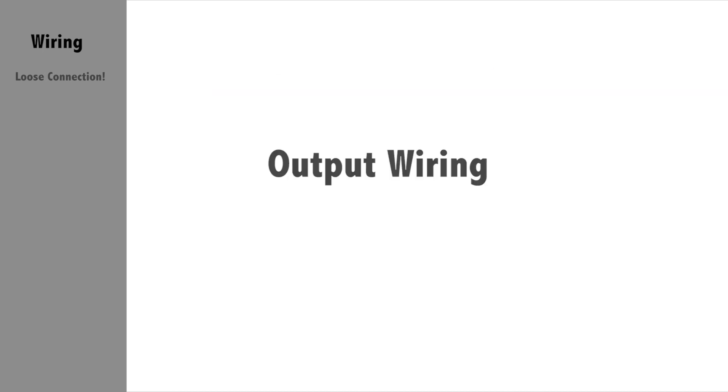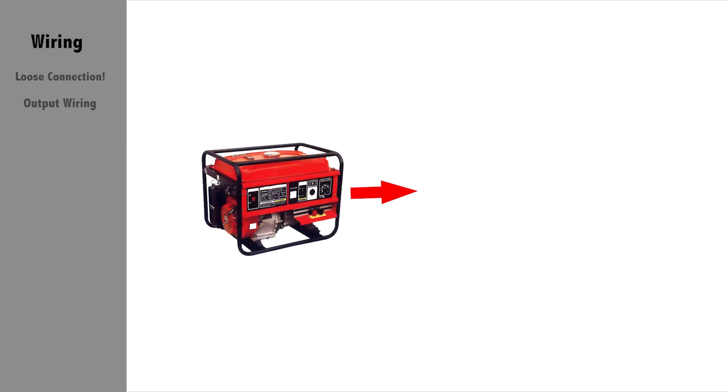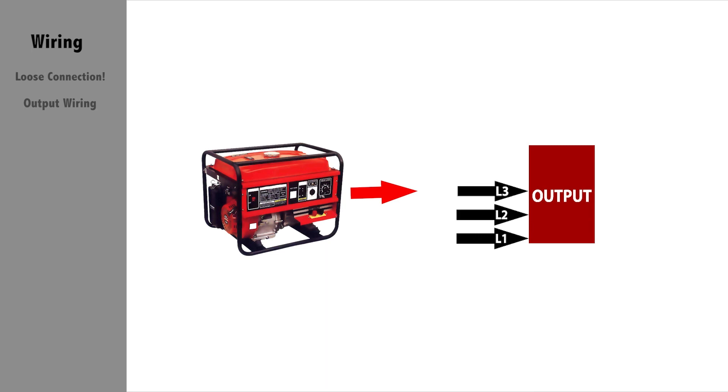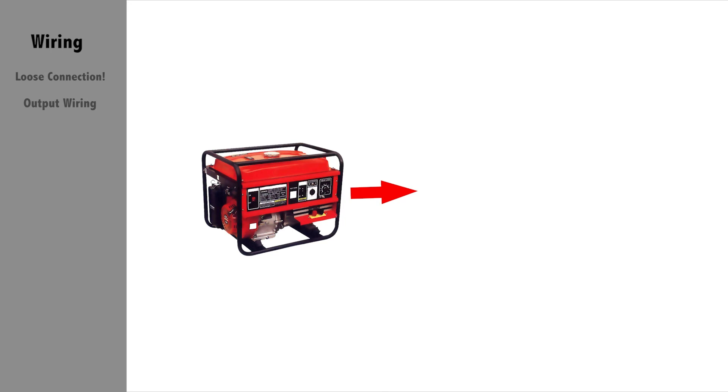Lastly, it is important that your generator's output wiring matches your Outback inverter configuration such as single phase, split phase, or three phase. If you are using a transformer for generator balancing, step up or step down, it's a good idea to check for trip breakers and connections within the transformer wiring.